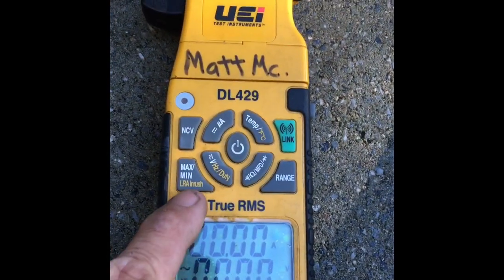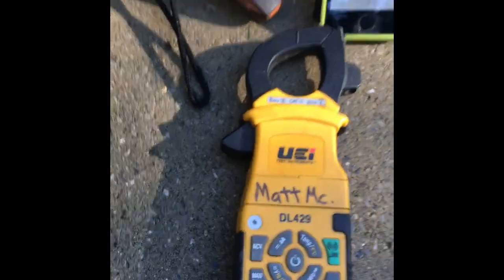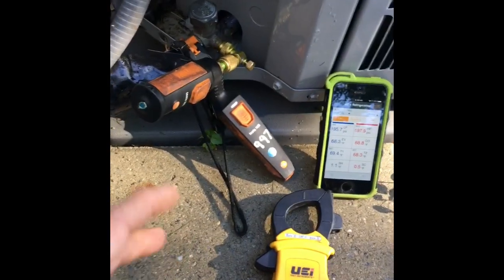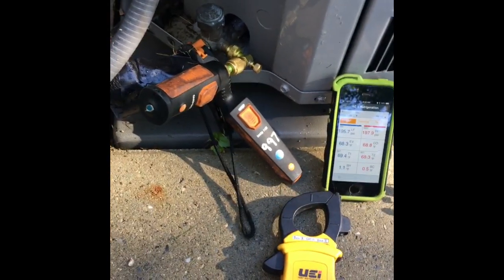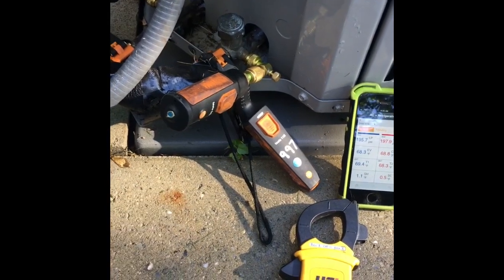You want a meter that will actually pick up locked rotor amp inrush. This meter has been picked on through the years, but it does have a locked rotor inrush function. I've got a true RMS — this is a pretty good meter, it's always been fairly accurate. This is great if you have lights dimming in the house or compressors going out on overload.